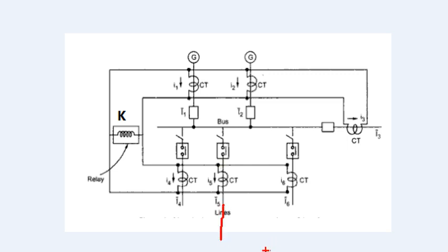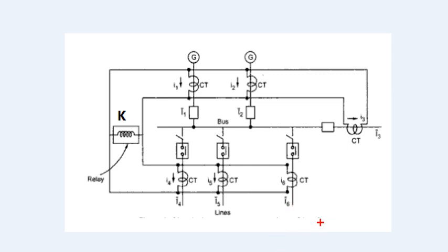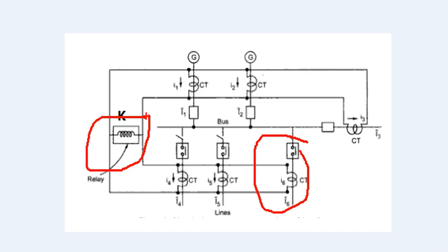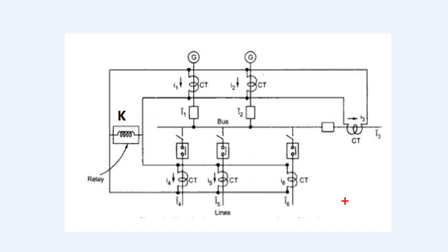We can use normal CTs, but we need a special iron core. Suppose there is a heavy fault outside the zone. In that case, the CT may become saturated. When the CT is saturated, it can produce a false differential signal. This is a sensitive issue — an external fault could cause the relay to trip the entire bus bar incorrectly, which is a problem we need to address.